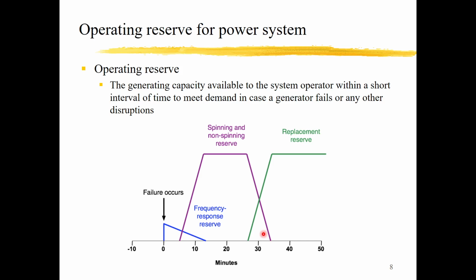Okay. So I also want to talk about the operating reserve. Here, we have 3 kinds of reserve. The first one is the frequency response reserve. This is the quickest, the fastest one. When a failure occurs, it has to respond in no time. This is followed by the spinning or non-spinning reserve, and then the replacement reserve. The operating reserve is the generating capacity available to the system operator within a short interval of time to meet the demand in case a generator fails or there are any other disruptions. For the power system, you always have to face failures of something and disruptions from the environment. Sometimes the grid is disrupted by a typhoon, by a flood, or something. So they always have to face that.